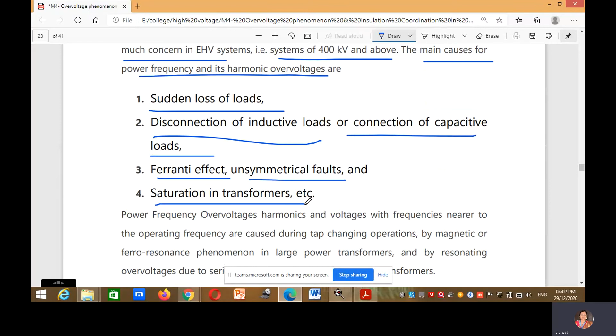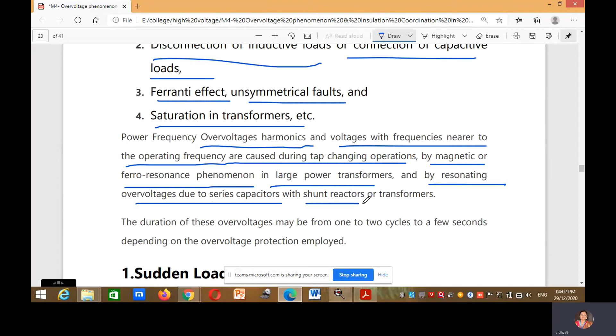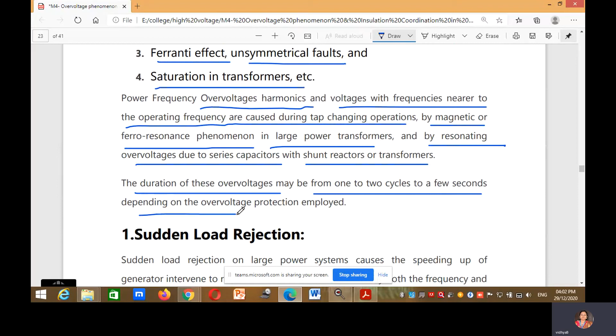Power frequency over voltage harmonics and voltages with frequencies near to the operating frequency are caused during tap changing operations, by magnetic or ferroresonance phenomena in large power system power transformers, and by resonating over voltages due to series capacitors with the shunt reactors or transformers. The duration of these over voltages may be from 1 to 2 cycles to a few seconds depending on the over voltage protection employed.